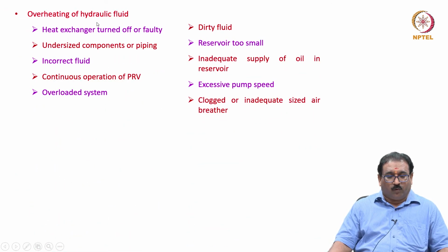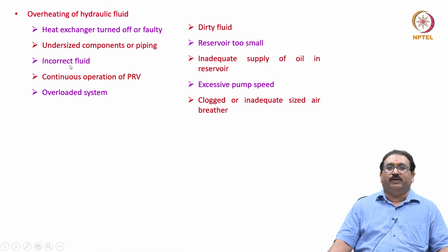If we come across overheating of the hydraulic system, what are the reasons? Heat exchanger turned off or faulty, undersized components or piping, incorrect fluid, continuous operation of pressure relief valve, overloaded system, dirty fluid, reservoir too small, inadequate supply of oil in the reservoir, excessive pump speed, clogged or inadequately sized air breathers.